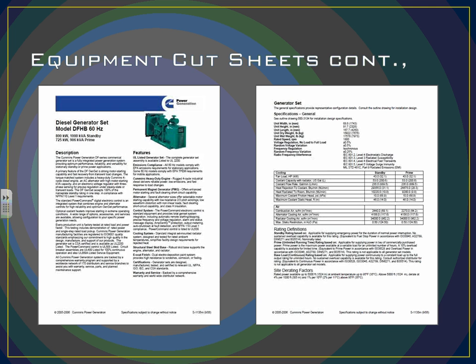We worked in the system of building our system from the ground up before we went and sized our generator for the power. You can work two different ways. For us, it was easier to do it this way because we didn't have experience right off the bat to know what we're going to need, because we have to work with anything in the future. So there are two different ways you can do that. You can size the switchgear based off of what this type of plant is going to be, if you have that experience. We went backwards. With the switchgear or the generator set, we're able to put in the information, and then Cummins can actually tell us what generator size we'll need.